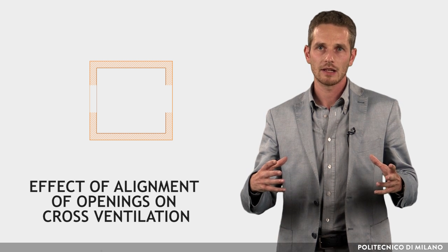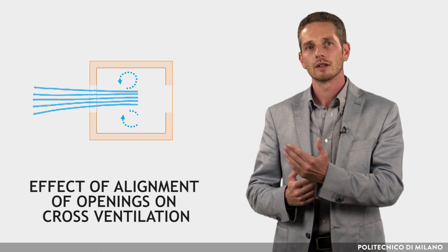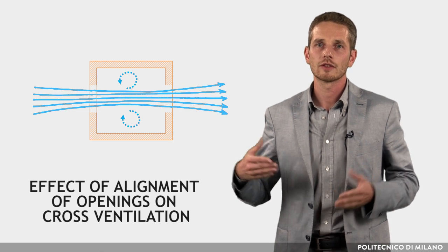When inlet and outlet openings are aligned, cross-ventilation is activated by wind. If the openings are aligned in the direction of the wind, the airflow passes right through the space, influencing a reduced part of it and giving rise to modest induced air movements.